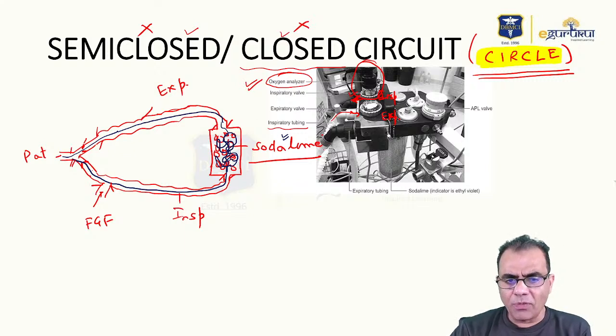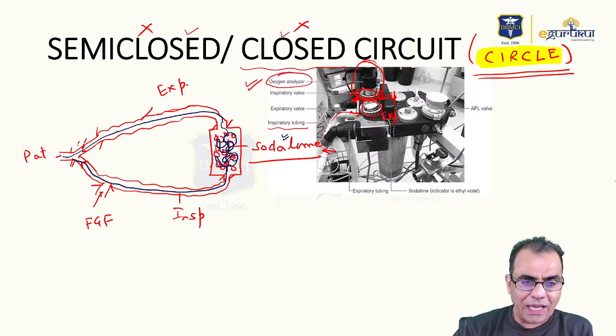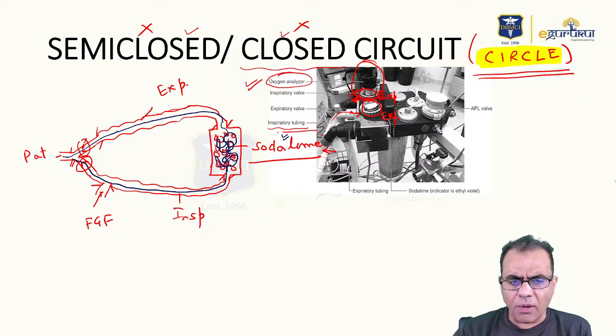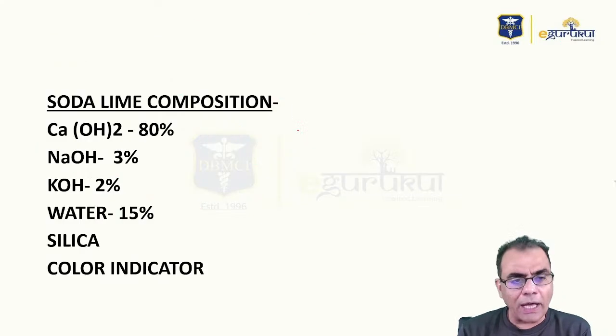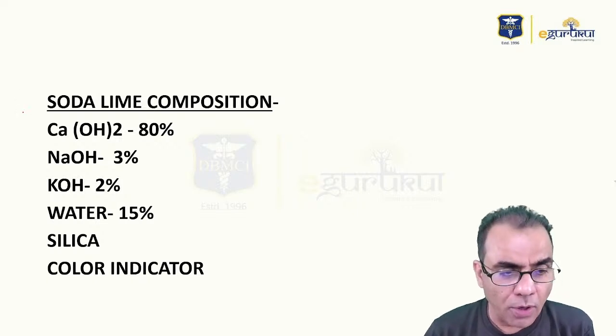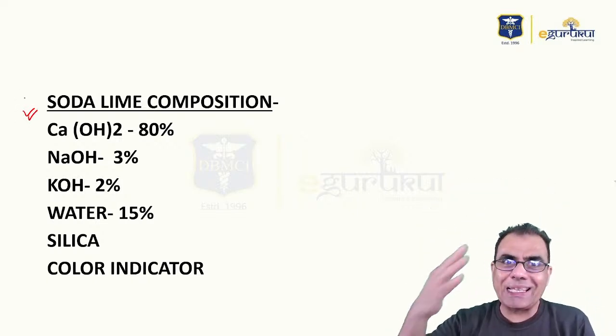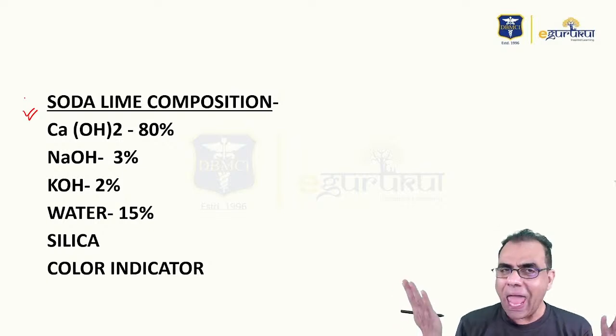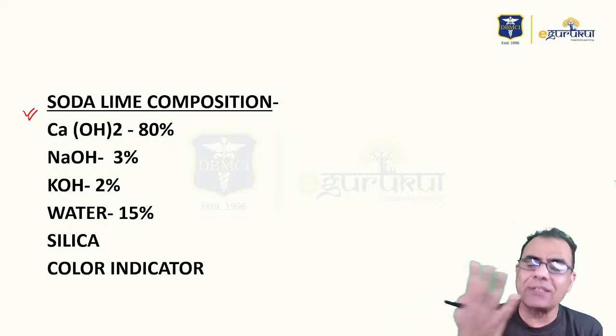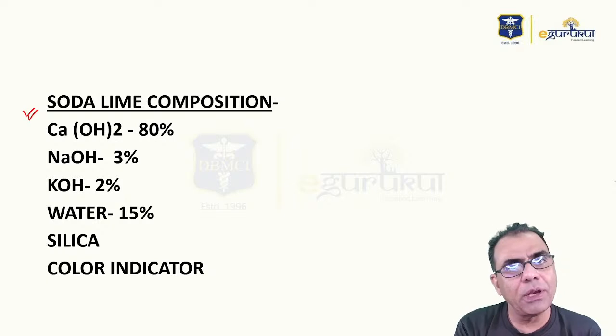And this another limb obviously will be the expiratory limb, and these are the valves I was talking about, which ensure that there occurs unidirectional flow of gases. So one of the very important components of the circle system is soda lime, because it is the soda lime which plays a major role. It absorbs carbon dioxide, and that is how the same gases can be reused.